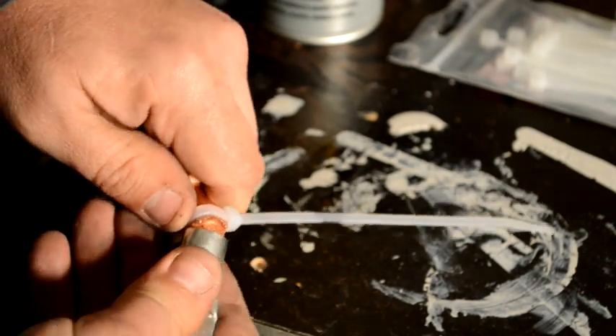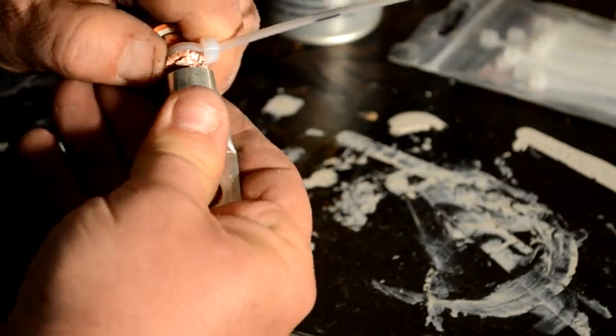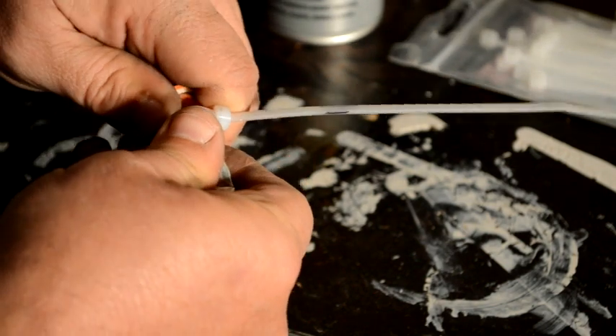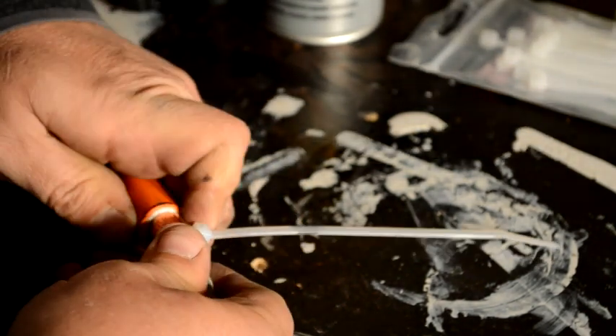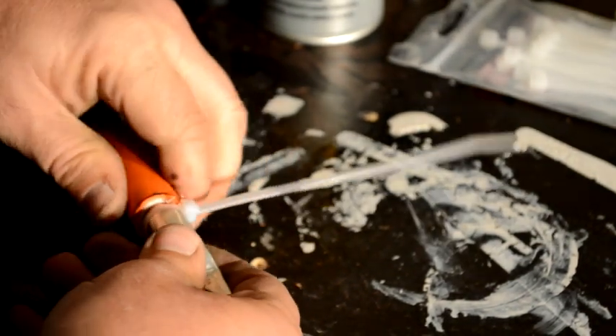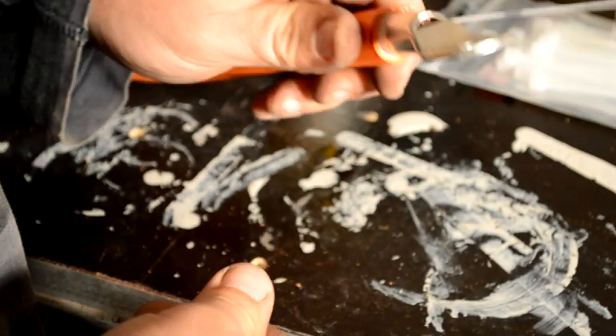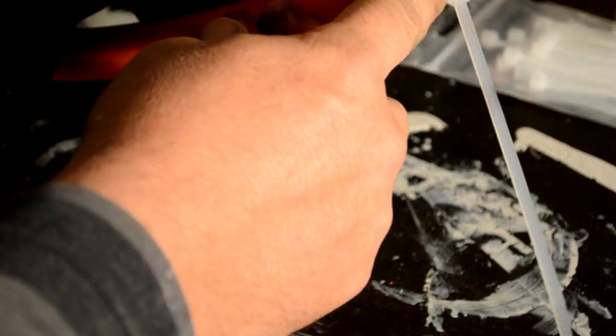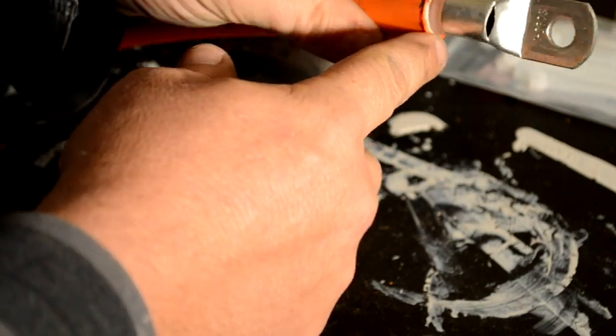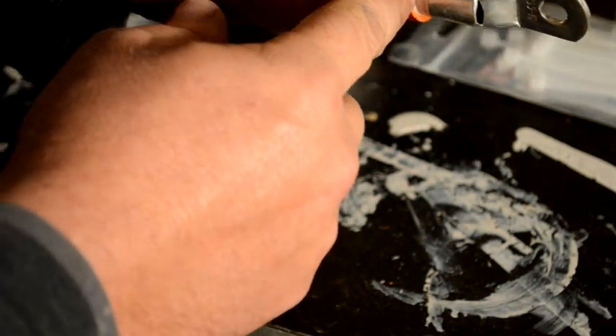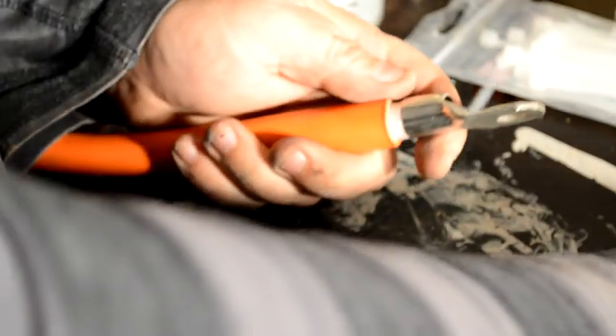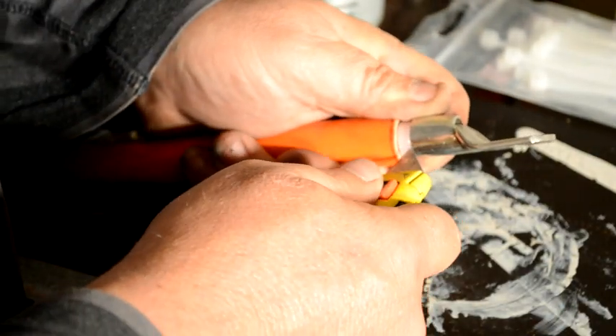Now you're not going to get all, you may miss a few, but that's okay. And then just push and slide on because of the lubricant. It's going to push the cable tie all the way down to the end. I've missed a couple of strands there, that's fine. Once that lug's gone all the way down to the end as far as it can go, grab your knife and cut the cable tie.